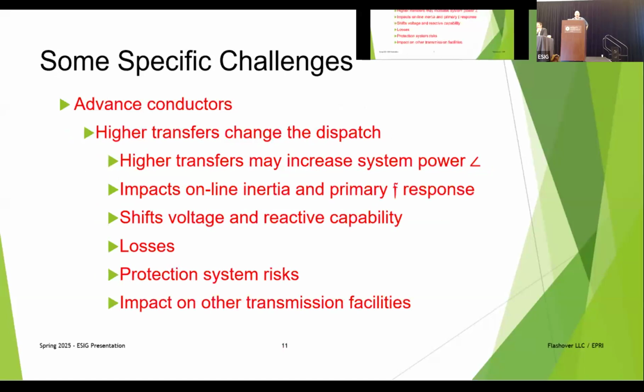Advanced conductors, good stuff. Everybody knows some of these conductors now will operate up to 250 degrees C. You can almost double the capacity of some of the circuits by replacing the old conductors with some of these new fancy conductors. Well, that's great, but it's being done to change the dispatch. And what does changing the dispatch do? Well, changes the power system angle across your system. And does that introduce problems you've never seen, specifically stability, voltage, and reactive performance? It also may impact your primary frequency response.